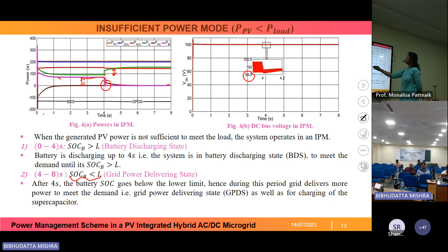Here we can see that the transient power is handled by the supercapacitor unit. During this condition, we checked the DC bus voltage, and there is only a 0.5 volt deviation at the DC bus when the state changes from battery discharging state to grid power delivering state.